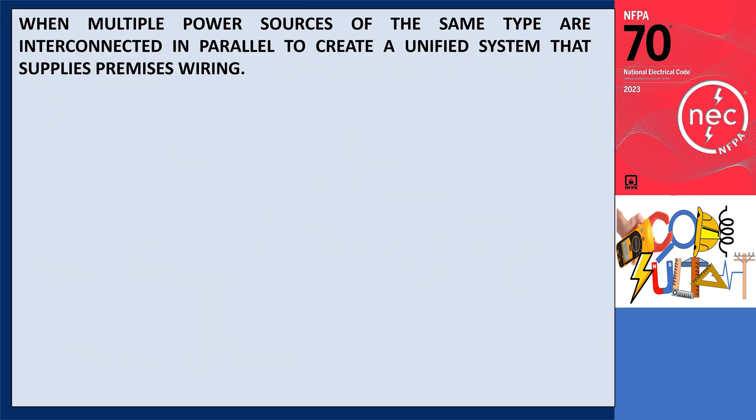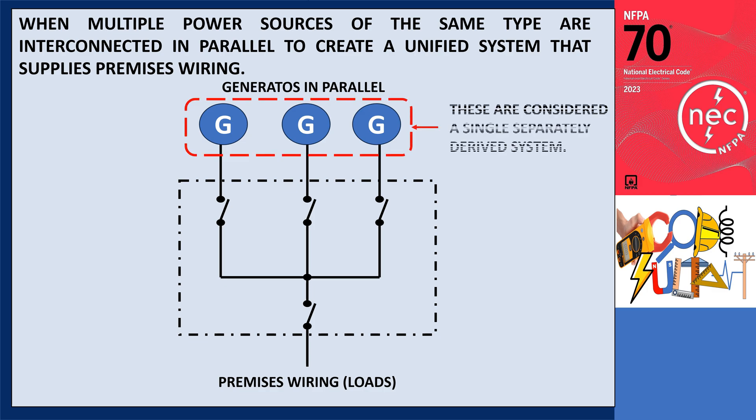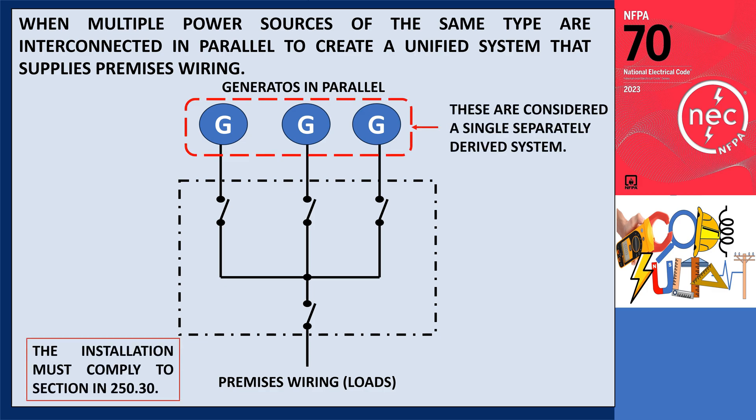Further, when multiple power sources of the same type are interconnected in parallel to create a unified system that supplies premises wiring, they are considered a single separately derived system. The installation of such a system must be carried out by the regulations stated in 250.30.